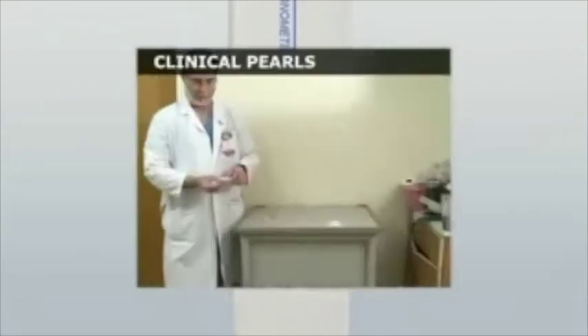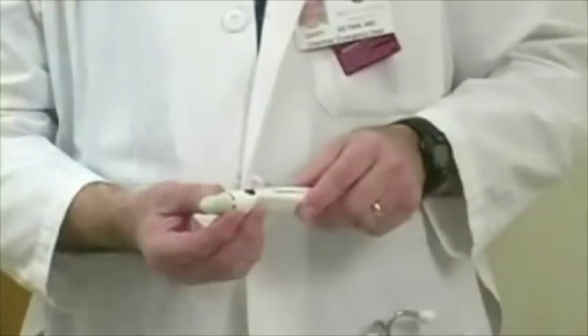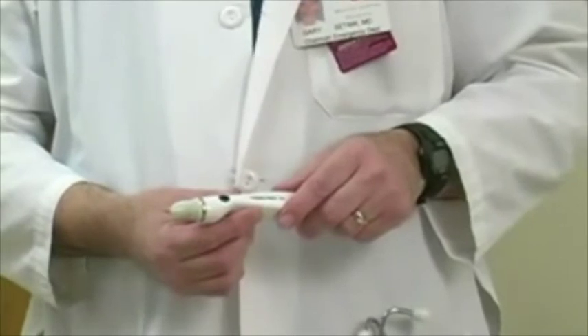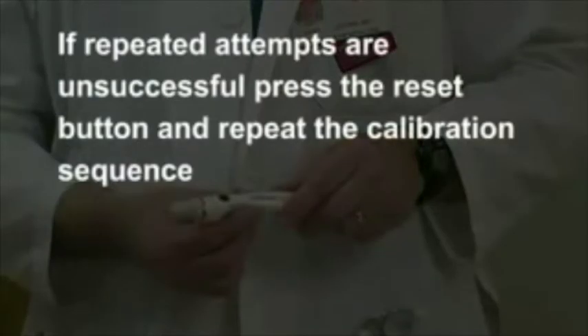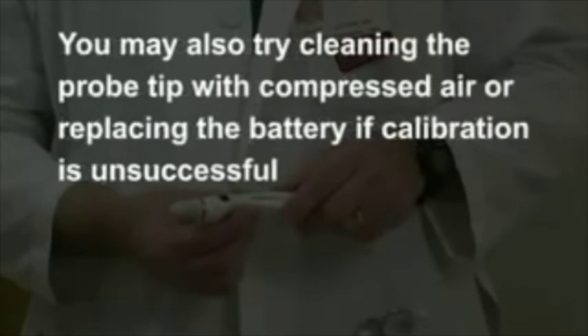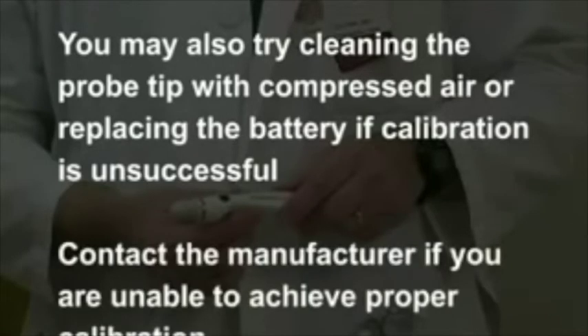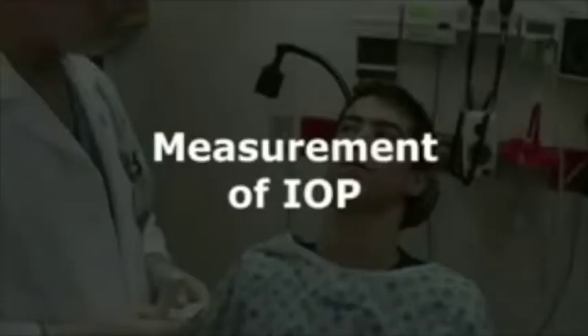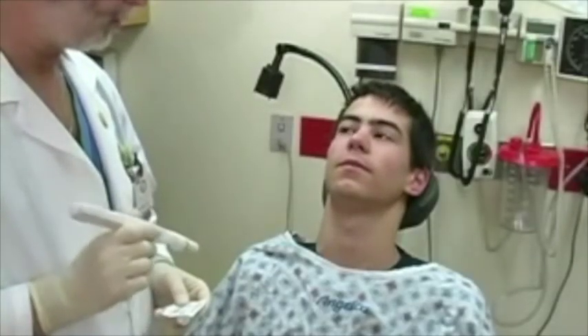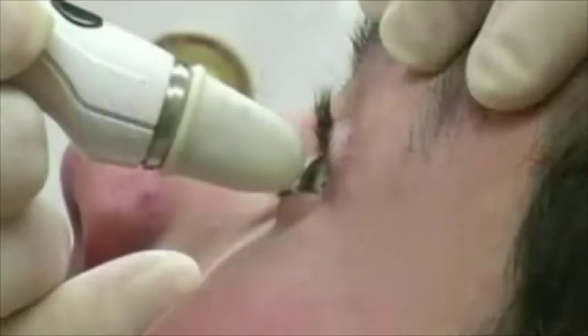If further attempts at calibration are unsuccessful, loosen the latex cover and repeat the process. If repeated attempts are unsuccessful, press the reset button and repeat the calibration sequence. You may also try cleaning the probe tip with compressed air or replacing the battery if calibration is unsuccessful. The patient may be positioned seated or supine during the measurement of the intraocular pressure provided the device is applied perpendicular to the corneal surface.